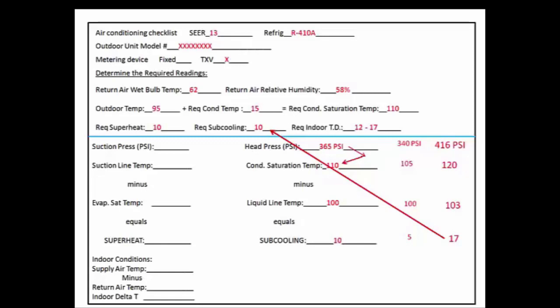By using our form here and looking at our subcooling, on a TXV system we can tell whether we have too much refrigerant in the system, not enough refrigerant, or just the right amount of refrigerant. If it's a fixed orifice metering device, then we're going to be looking at our superheat. But on a TXV unit, we're going to use subcooling.